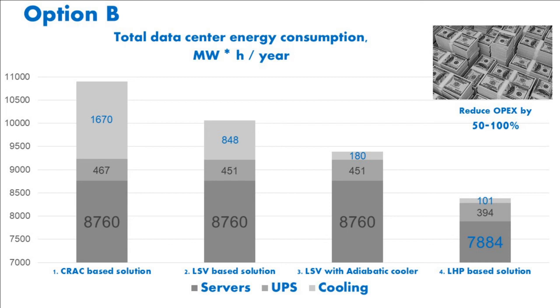On this slide you can also see an increase in the reliability of the system. If you look at the energy consumption of cooling systems, in the second case it is half as much thanks to the low-speed ventilation and a higher temperature for free cooling. The chiller works 3 times less and its service life is longer. And in the third and fourth case, chillers are simply absent. Thereby, we get a more reliable solution with an interesting bonus on the next slide.